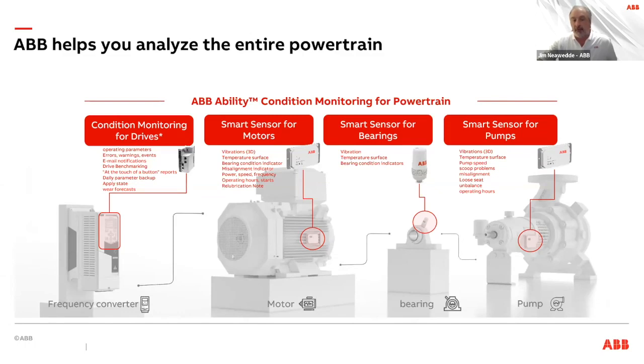And we've actually had some cases where, with the smart sensor, we were able to identify problems early on. In this particular case, the motor was being sent out for rewinding. It came back, and it had not been rewound properly. The smart sensor immediately detected that the motor had not been reinstalled properly, and we were able to address this. It didn't cause any plant downtime. We were able to shift this to a maintenance period when they weren't running production. And so it saved a lot of money just by being able to detect that the motor was about to fail.